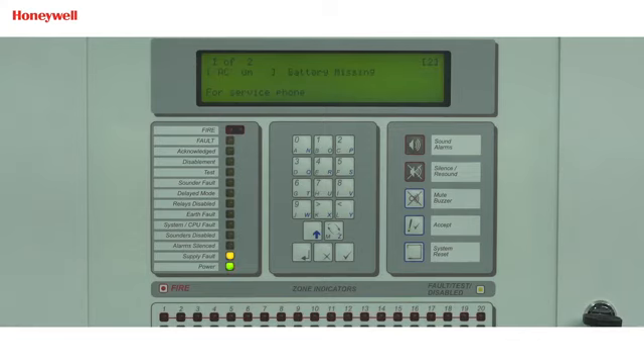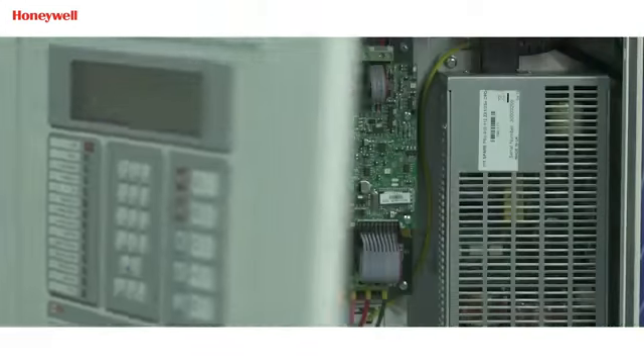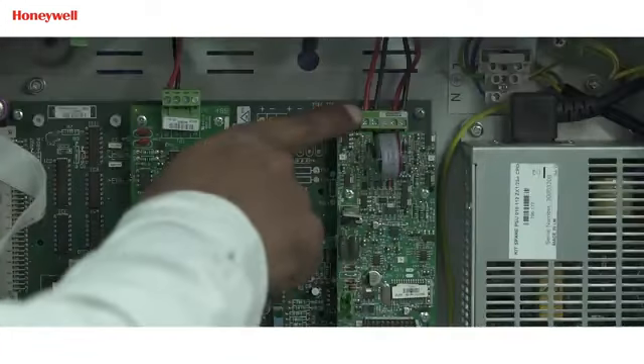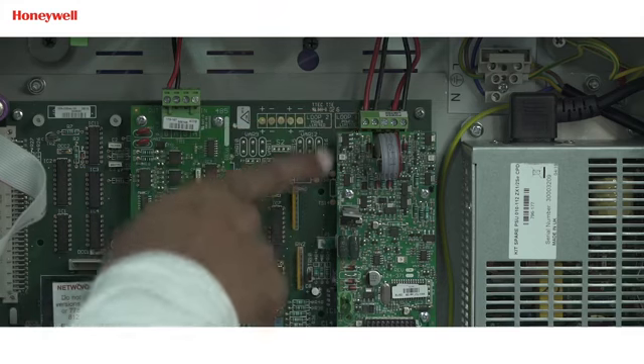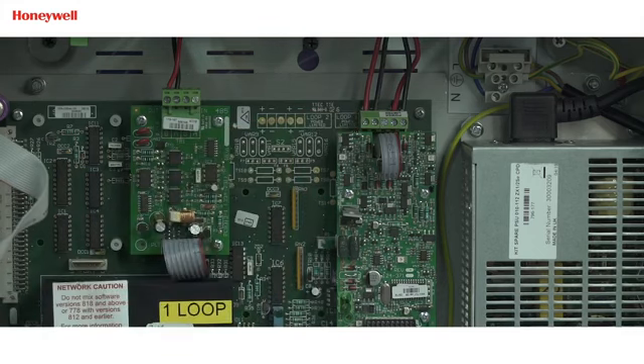First, we will start with the connection part. Power down the panel, open the panel door. On the baseboard, you can see terminal TB1 at the top right corner, which is the terminal for loop 1, where we should connect field wiring at loop.